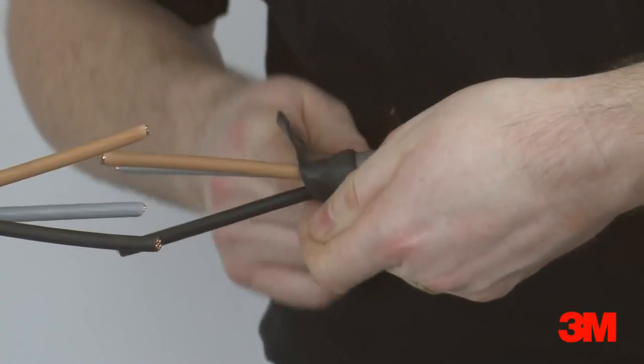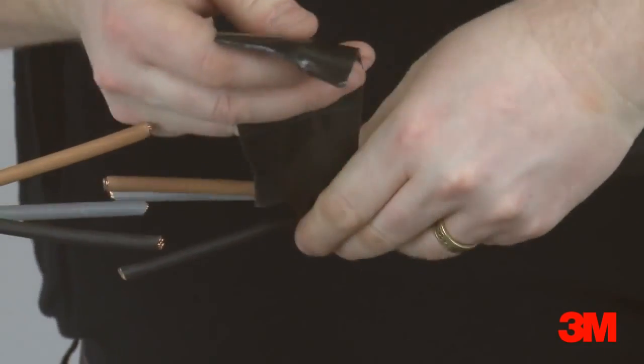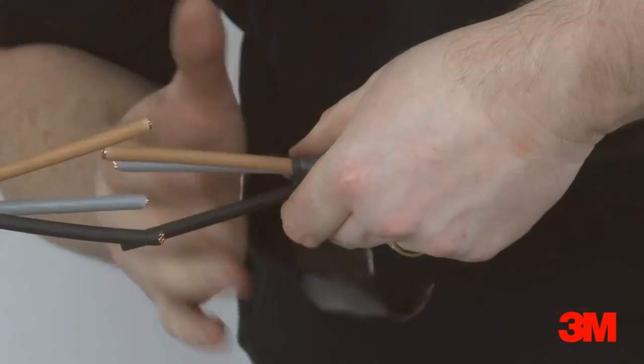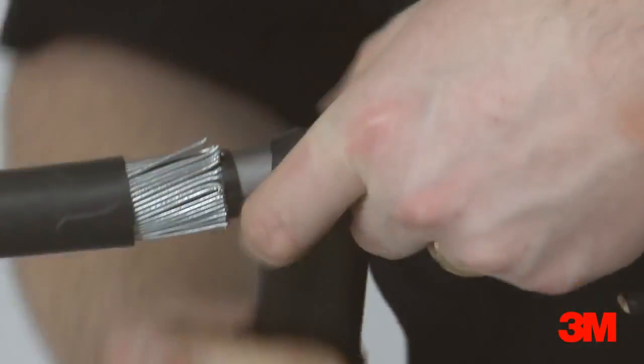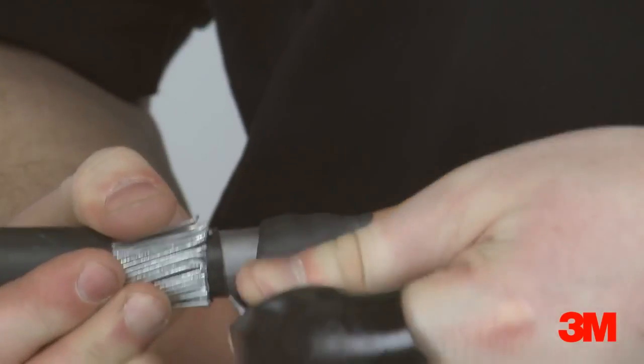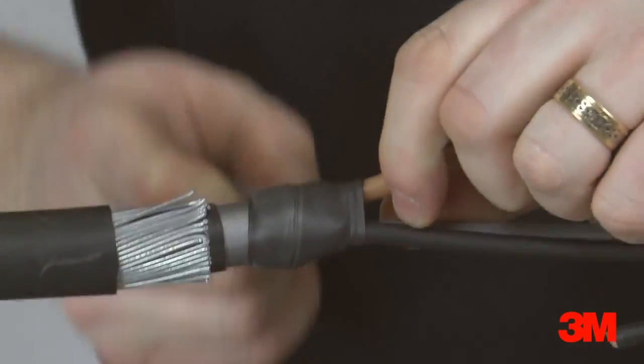Scotch 23 self-amalgamating tape is used to seal the crutch of the cable. Scotch 2228 mastic tape is then applied over the inner sheath, finishing 5mm into the lead sheath.